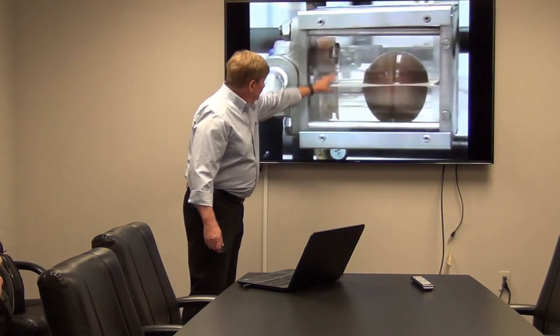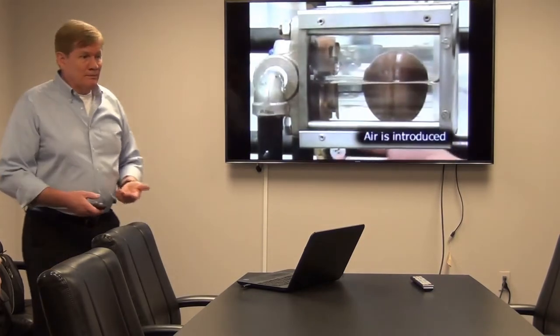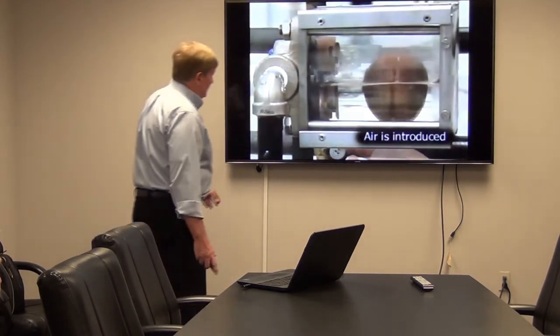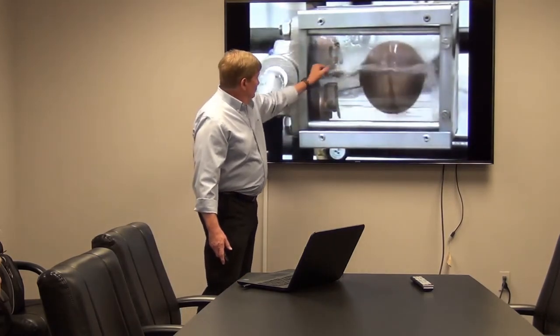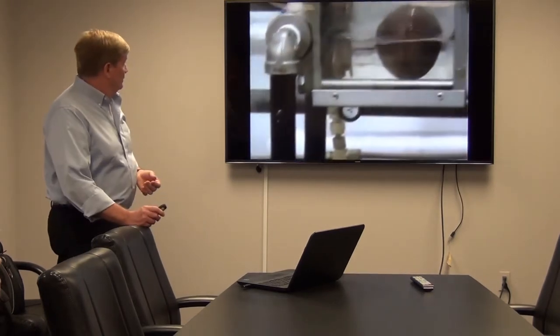There's a little air vent. So you really have two traps in one, and it addresses all the issues when you're doing process temperature control, modulating control. It allows air to discharge right through and doesn't cause a trap to fail closed or go to a closed position.